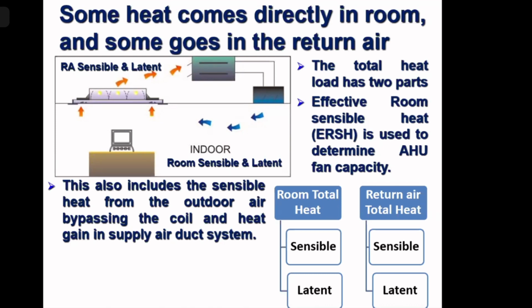Because fan motor is not generating any moisture. It's giving only raw heat. So it gives only sensible heat. So that sensible heat from the fan motor, where it will come, whether it will come to the supply air part, I mean the room sensible heat part, or it will go to the return air sensible part, that we'll see. But that has also to be taken. And all these taken together is called effective room sensible heat. And this effective room sensible heat determines the size of the air handling unit fan. Next.